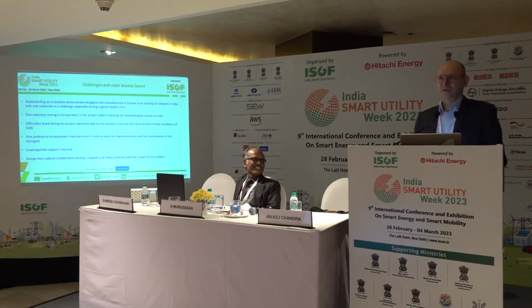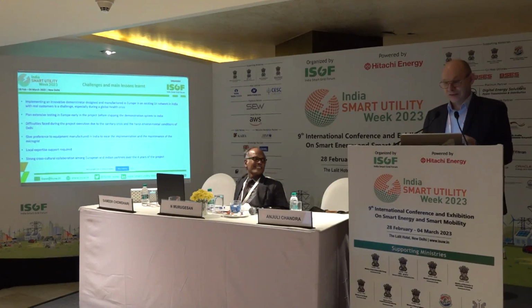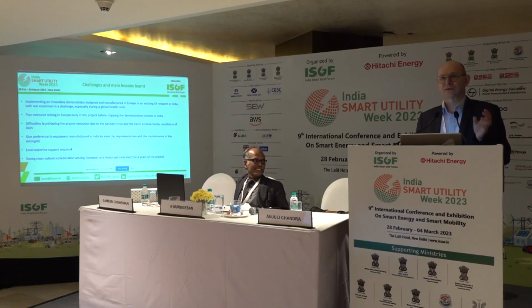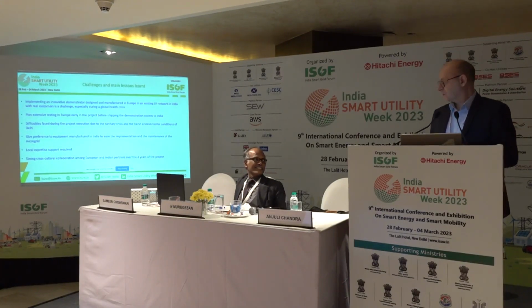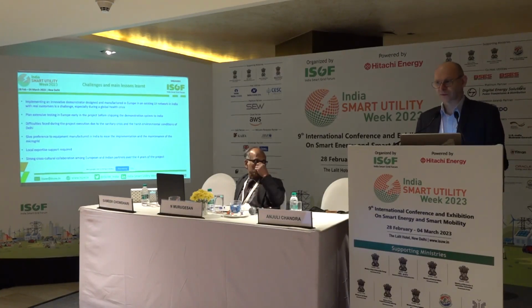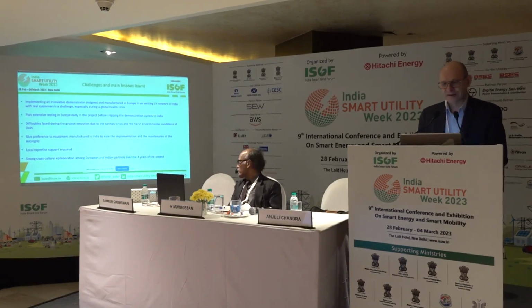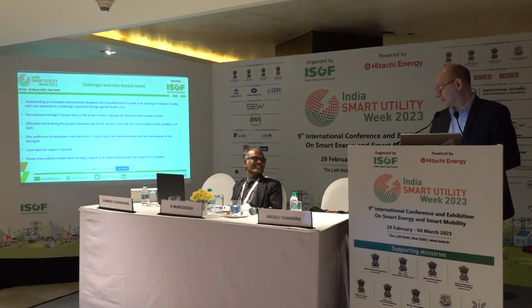We also had to change things, one difficulty to put a microgrid in operation in place due to the size of the battery—I mean the short circuit currents are too small. So we had to change this, and these are tricky things to be done. We had to change the protection relays also, and adapt to the real conditions of the substation. This equipment has been designed in Europe, so it's quite difficult for Indians also to maintain. So this is also a little bit tricky.